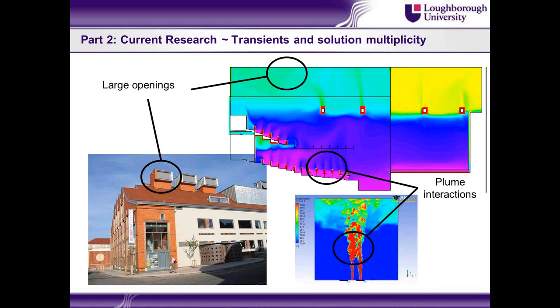So when I did this computational fluid dynamics simulation, I ran it in the steady state, i.e. I forced the software to find a steady state solution, which it did. And we've got the layer of warm air here, which is above head height, and that drove 6-7 air changes per hour as required. Fresh air came in at low level. It all worked okay. But it doesn't pick up what might happen if you model it in a dynamic, transient way.